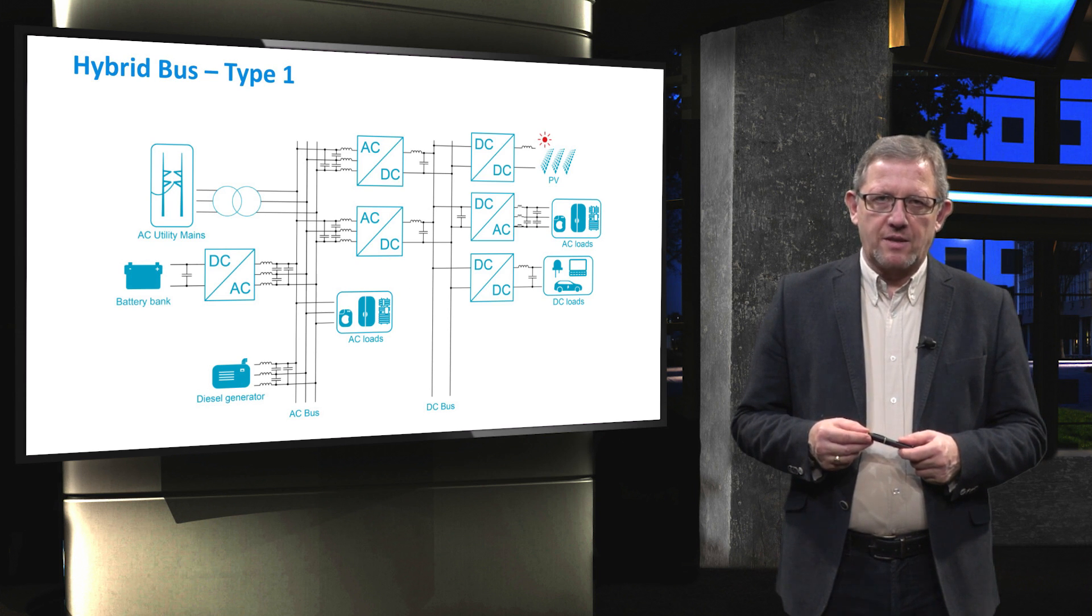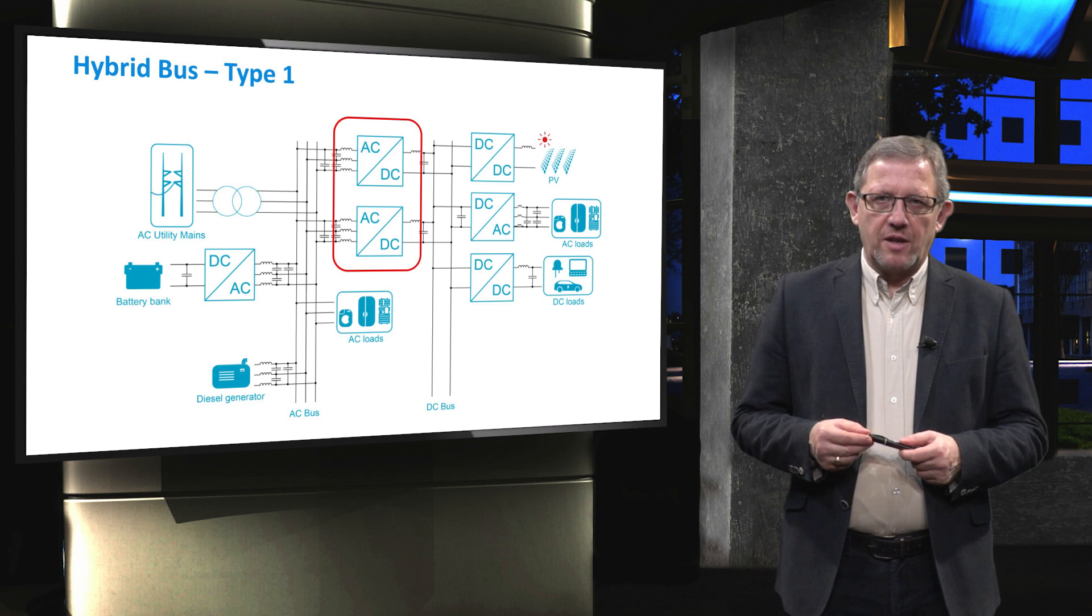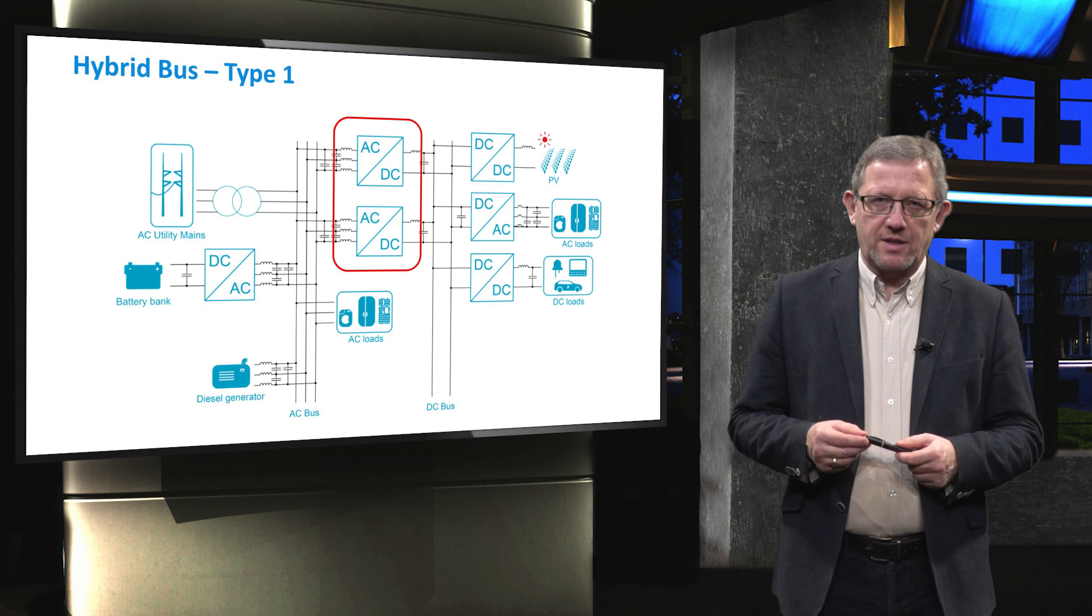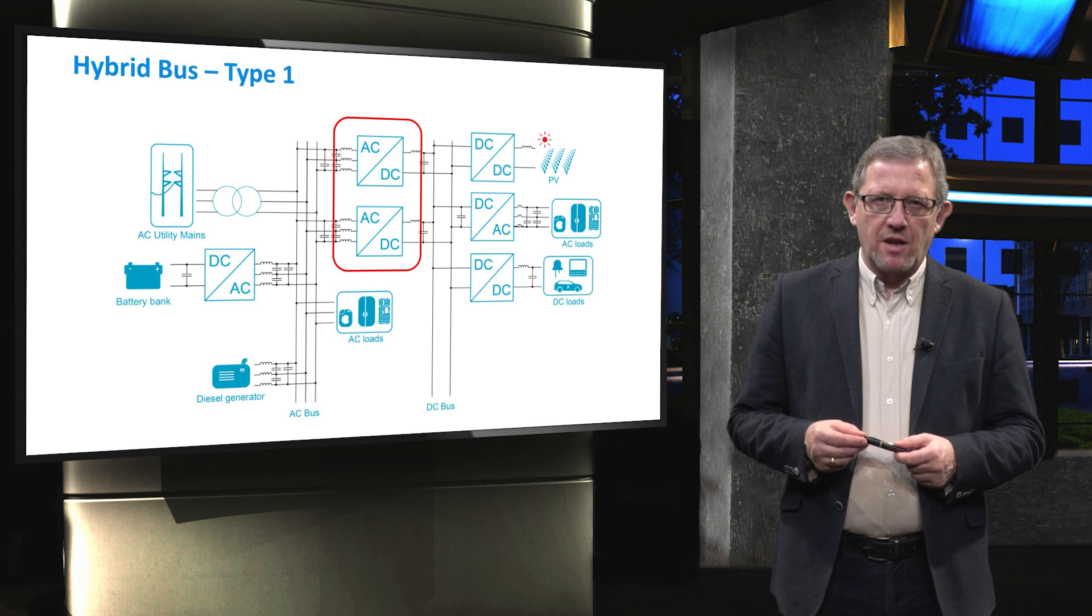The first type of hybrid bus is shown on the slide. The hybrid layout typically consists of one or more DC links connected to the AC ones. In the figure, two AC-DC converters are placed between DC and AC buses. This is mainly to achieve higher reliability in case one of them fails to properly operate and also to increase the power transfer capacity between AC and DC bus.